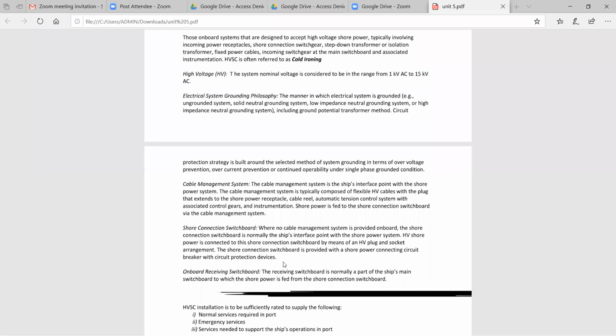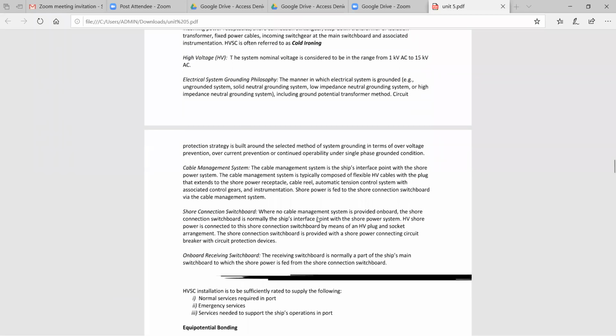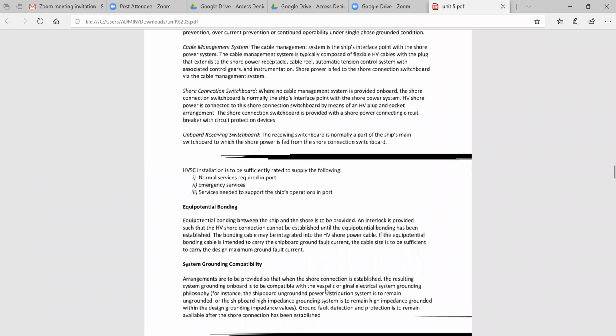Next one is the shore connection switchboard. The shore connection switchboard is very, very essential, because the high voltage shore power is connected to it. The shore connection to the switchboard is by means of a high voltage plug and socket arrangement. The shore connection switchboard can be provided at the shore power connecting circuit breaker through the protection of your devices. So this operation can be considered for an HVSC installation sufficiently rated to supply: the normal service required in the port, the emergency service required in the port, and the service needed to support the ship operations in port. Based on these three considerations, this operation is performed.